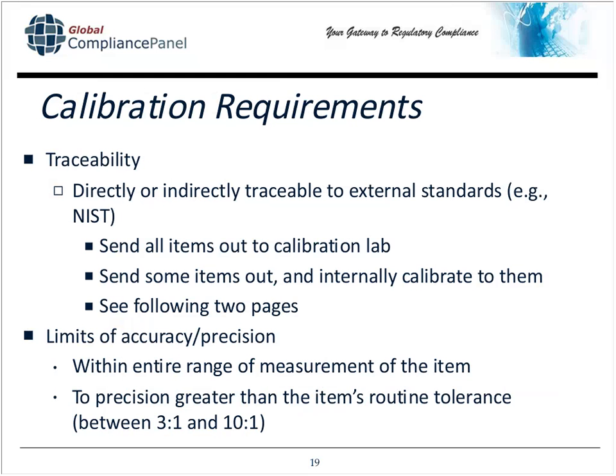You want to make sure that when you send those weights out to be calibrated at the calibration lab, the calibration of those weights is traceable to the NIST standard. And that way, your scales are indirectly traceable to the external standard. Take a look at a couple of pages that will give us some information. When you look at the limits of your accuracy and the limits of your precision, you want to make sure that you use the entire range of measurement of the item.